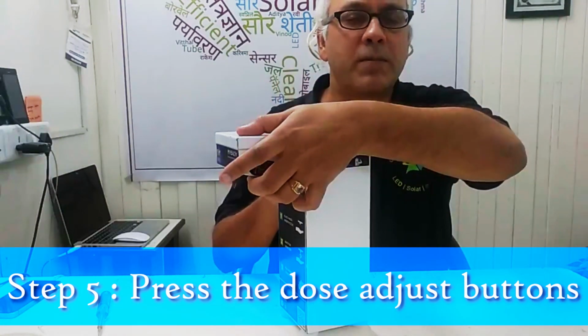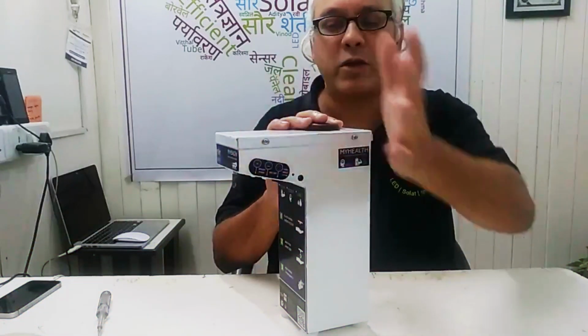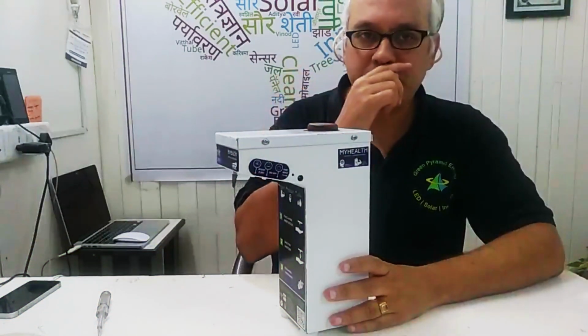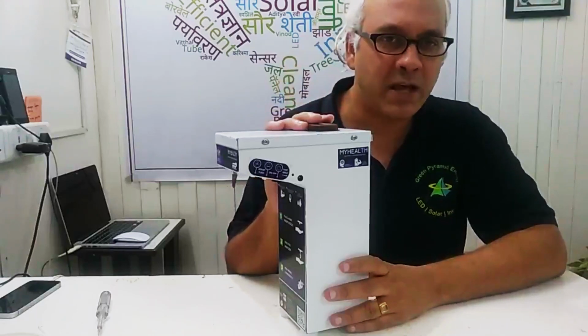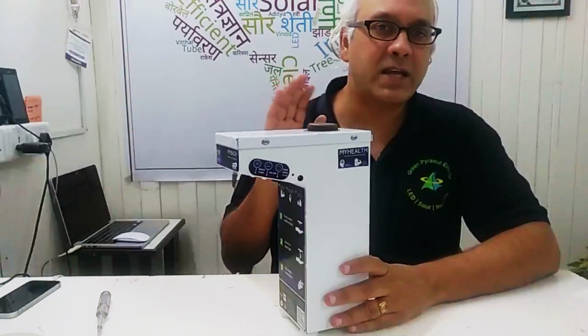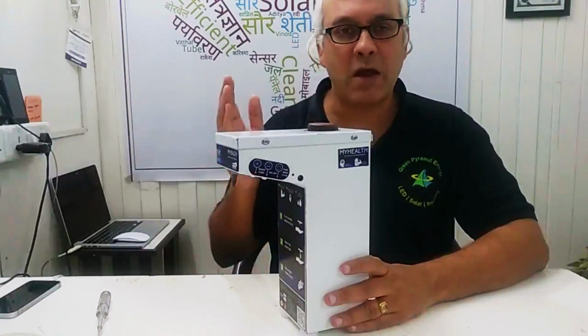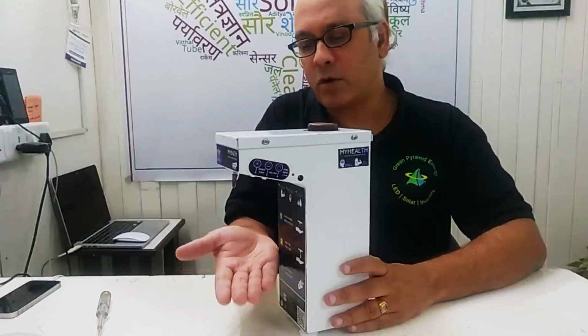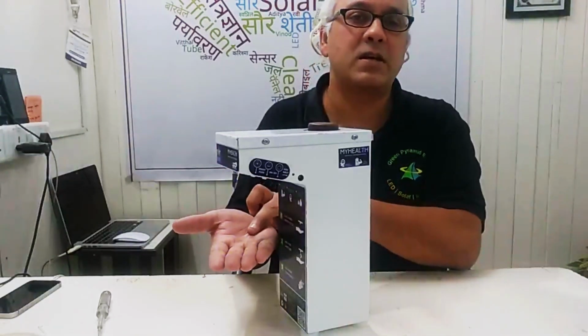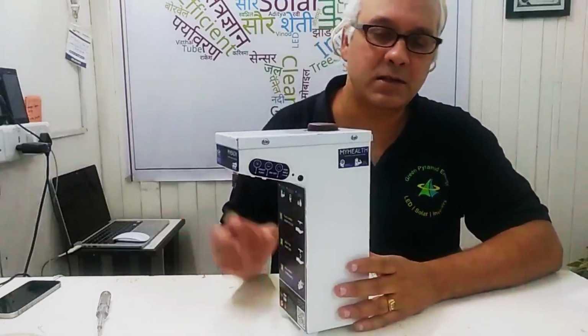Now if you're happy with the setting, just press both the dose adjust buttons again together like you did to come into the mode. And when you do that, you will hear a loud beep that tells you that the values have been saved and that the machine has come back into the regular operation. So now if you see, I will give you a demo. So now the machine has adjusted itself to this distance.